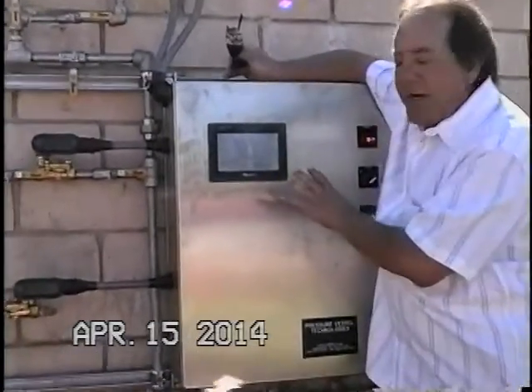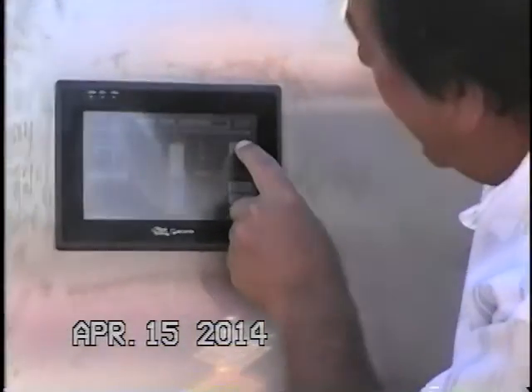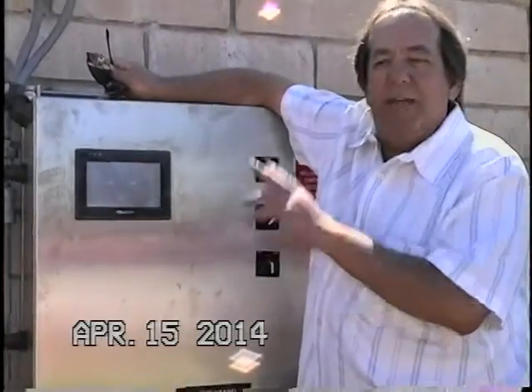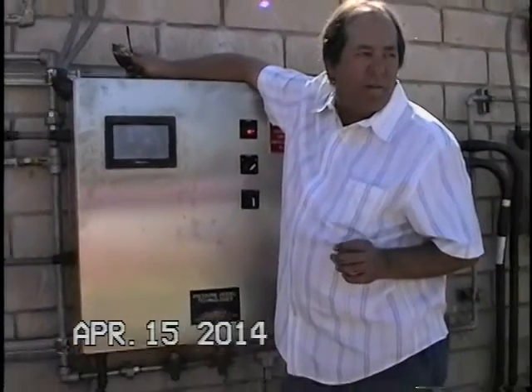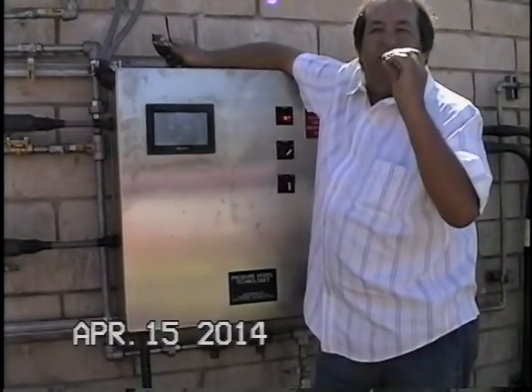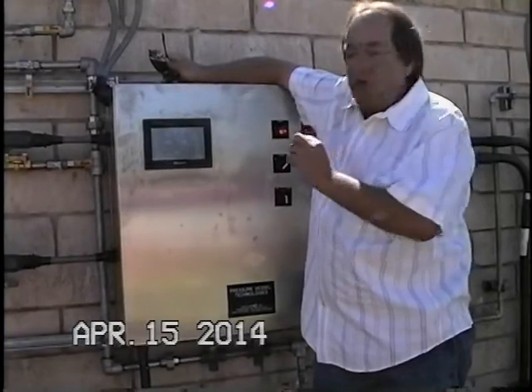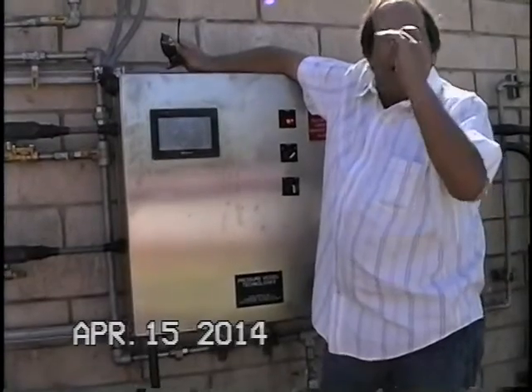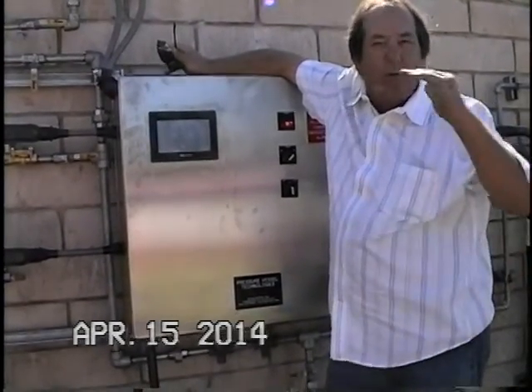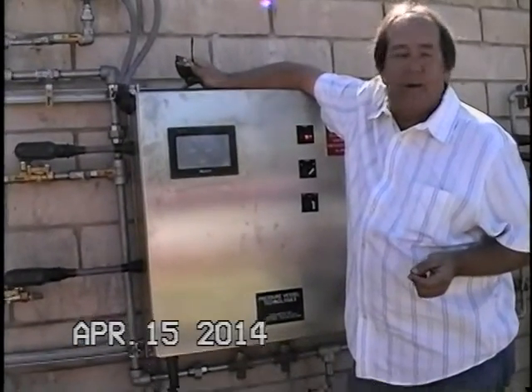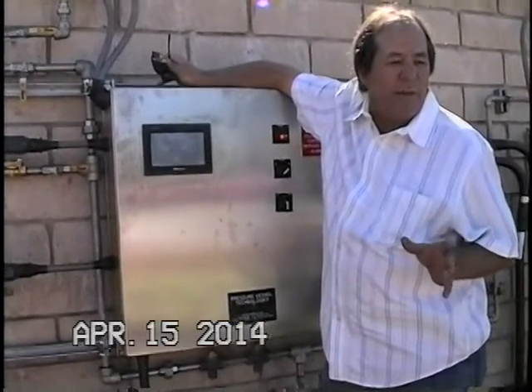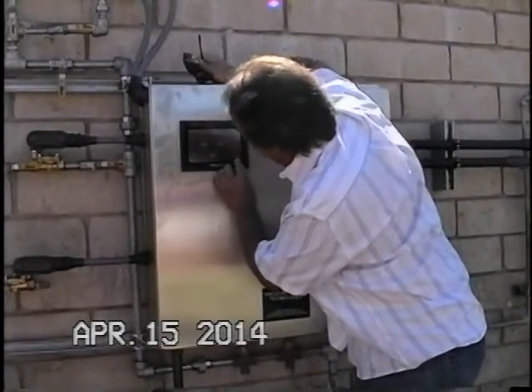In this main screen, which is a touch screen, at the very top we have that calibration section that I was telling you about. That's for the offset that we put in, because the tank probe is up above the bottom of the tank. If we didn't have that, it's only going to read what the probe's seeing. With this offset, that gets us to the real-time reading, and that is adjustable. If you find that you're a 1/4 inch off on that 48, you can go in and put that 1/4 inch into the offset to make sure they're reading exactly what they're supposed to be. Right now, it appears we're still well within any type of calibration levels. And you can exit out of that.